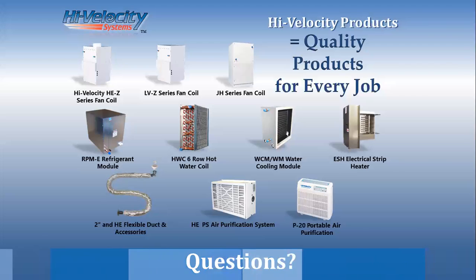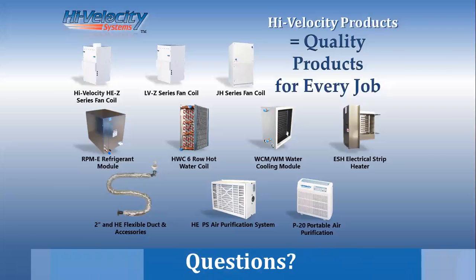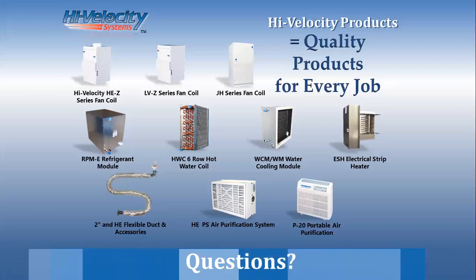No, that's awesome. So we do have another question. How can this unit be utilized in an Energy Star house since excessive length and coiled duct runs are prohibited? The duct runs, if properly designed, do not need to have the coiled flexible duct. We would prefer to design the duct system to an engineered level where all of our lengths meet the minimum of 5 feet length, and they do not need to be coiled.